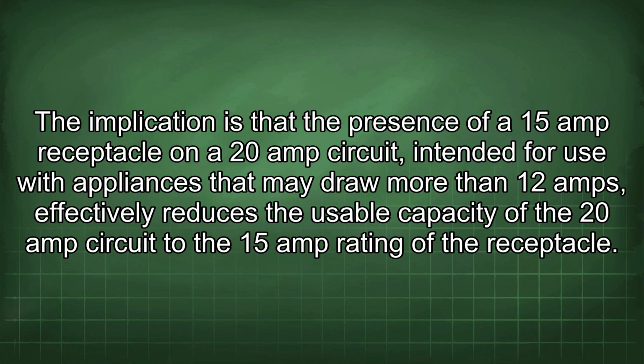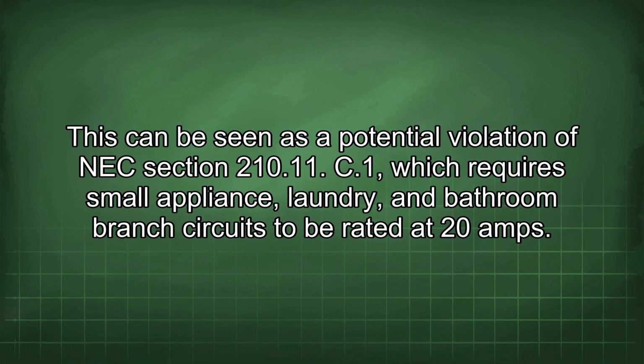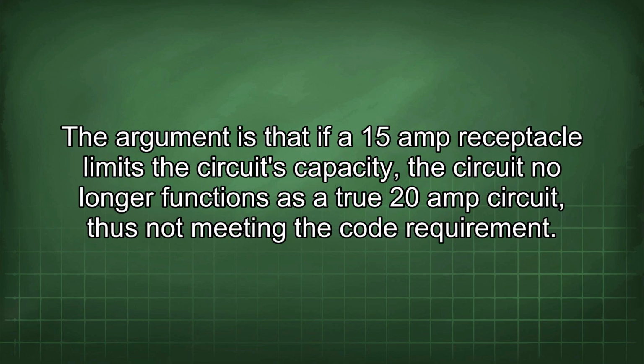The implication is that the presence of a 15-amp receptacle on a 20-amp circuit, intended for use with appliances that may draw more than 12 amps, effectively reduces the usable capacity of the 20-amp circuit to the 15-amp rating of the receptacle. This can be seen as a potential violation of NEC Section 210.11(C)(1), which requires small appliance, laundry, and bathroom branch circuits to be rated at 20 amps. The argument is that if a 15-amp receptacle limits the circuit's capacity, the circuit no longer functions as a true 20-amp circuit, thus not meeting the code requirement.